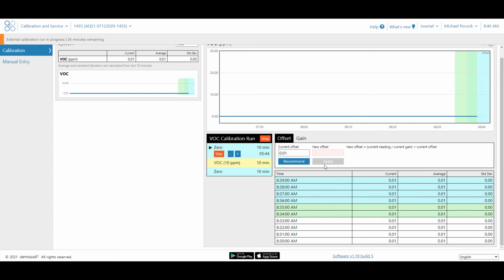So, okay, guys. So that's how you do a zero calibration. You should also do this at the end, after you have used the VOC cylinder. I recommend putting the zero cylinder on again, just to check that you are getting that zero reading. So I'll do it for 3 or 4 more minutes at least. I would do 10 if you're going to be abiding by the manufacturer's recommendations, 10 full minutes. And as you can see here, it's now changed to 0. So I made that small offset of 0.01, and now we're reading 0. So that's about it for a zero calibration.